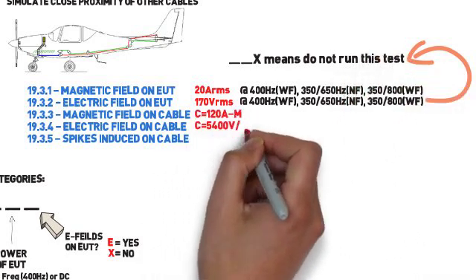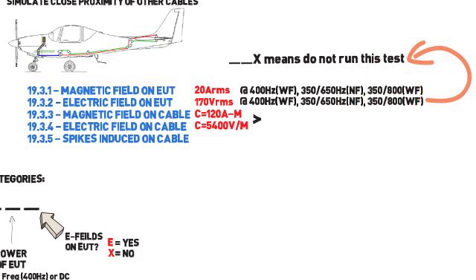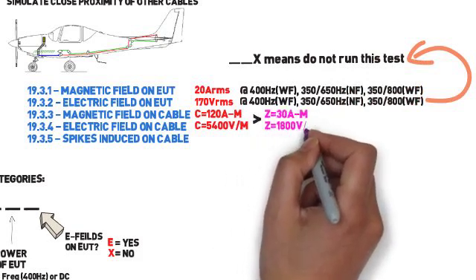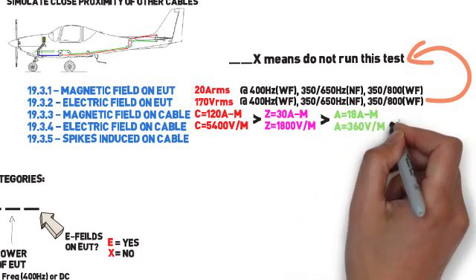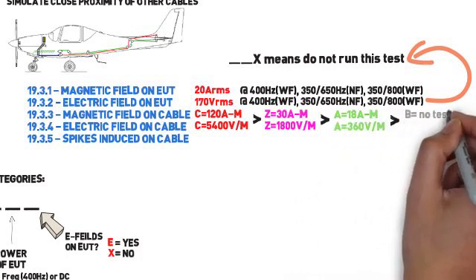Test levels for magnetic fields and electric fields on the cable are a little less straightforward, but you can easily compare the categories by looking at the max across the fundamental frequency. C is the most severe, followed by Z, A, and B.